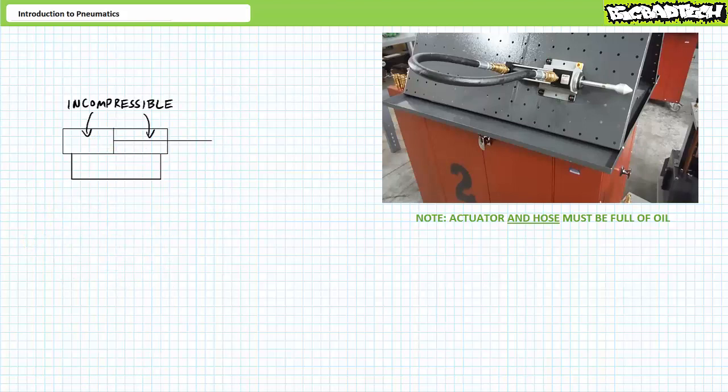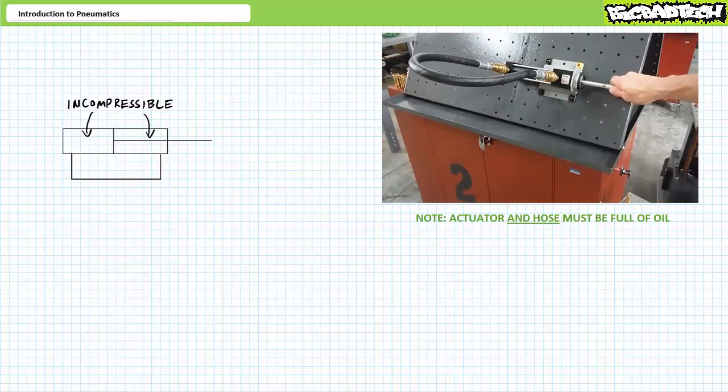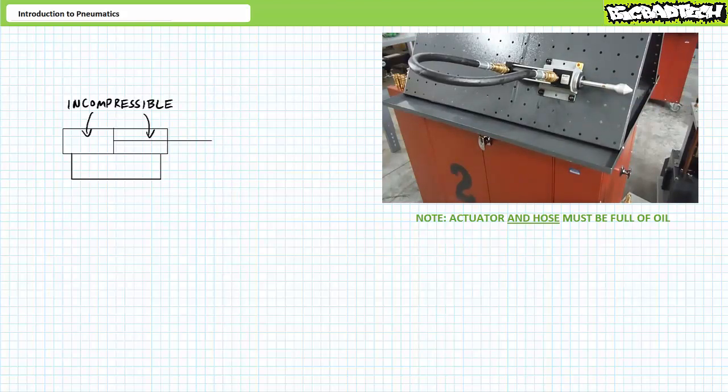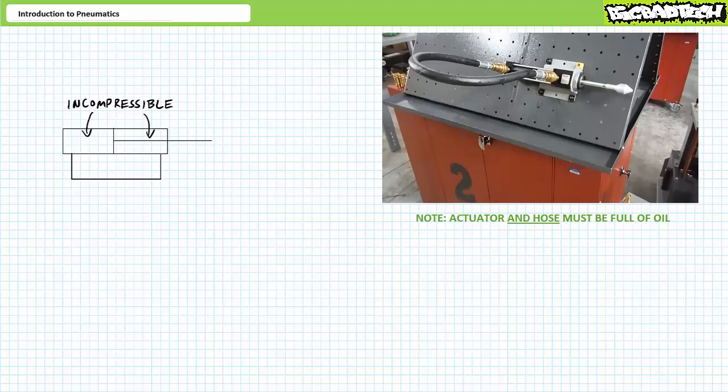If retraction won't work, can an external force pull the rod out? The answer again in practice is no. The act of extension necessitates the smaller rod end volume to be stuffed into the larger cap end volume. This isn't as easy as you might suspect because the missing volume in the cap end needs to be filled by something. I suppose you could pull hard enough to make the oil on the cap end transition to its vapor phase, i.e. induce a pre-cavitation event, but that's a less than ideal special case scenario.